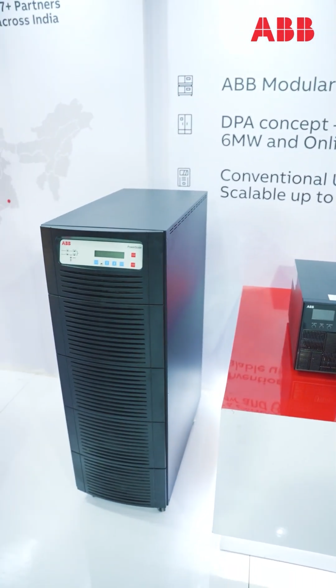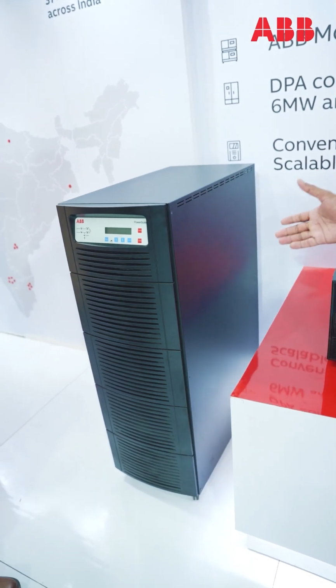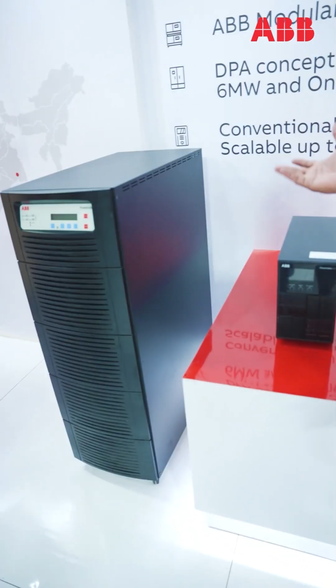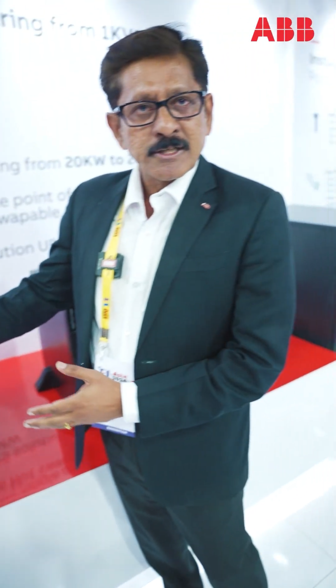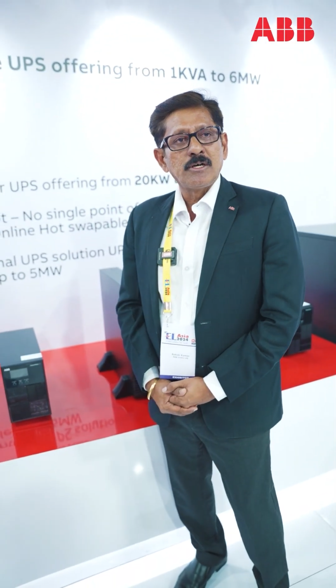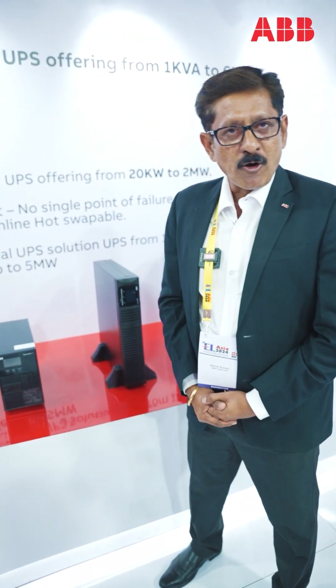Apart from that, we have three-phase input to three-phase output UPS systems. The range starts from 10 kVA. Here we can give a solution from 10 kVA to 5 megawatt UPS systems. This is a unique product range. When it comes to 60 and above, it's a unity output power factor.